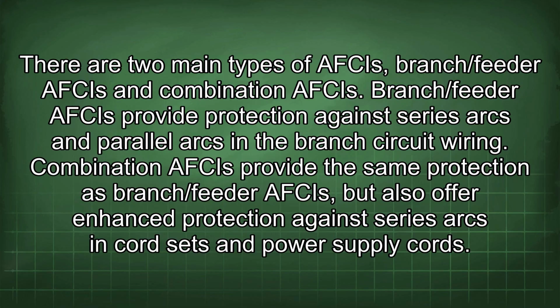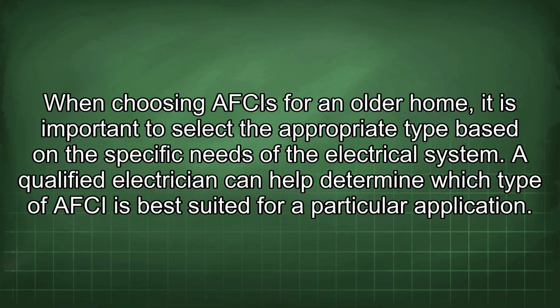There are two main types of AFCIs: branch/feeder AFCIs and combination AFCIs. Branch/feeder AFCIs provide protection against series arcs and parallel arcs in the branch circuit wiring. Combination AFCIs provide the same protection as branch/feeder AFCIs, but also offer enhanced protection against series arcs in cord sets and power supply cords. When choosing AFCIs for an older home, it is important to select the appropriate type based on the specific needs of the electrical system. A qualified electrician can help determine which type of AFCI is best suited for a particular application.